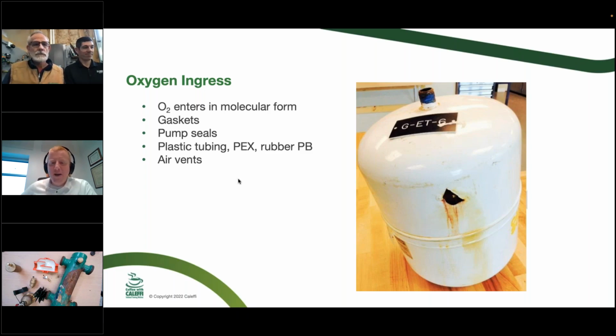Sorry about that. We had a good question that came in about hanging expansion tanks from the bottom of an air separator. We have a tapping on the bottom of our air separator, but they asked about the idea that is it possible for dirt and debris to actually come from that air separator and fall down into the expansion tank? And is that a problem? Is that something that needs to be addressed? Yeah, certainly. I mean, again, think of that low velocity zone.